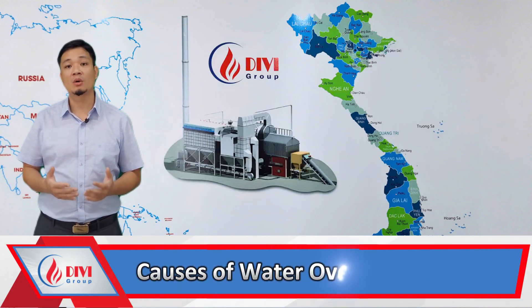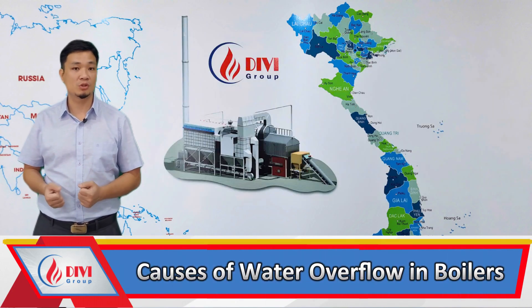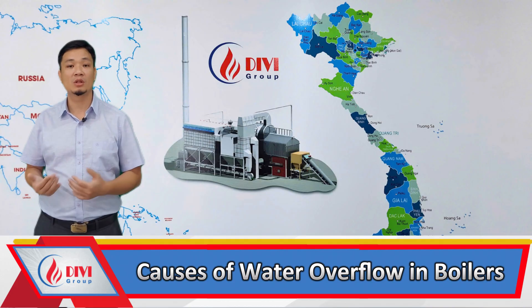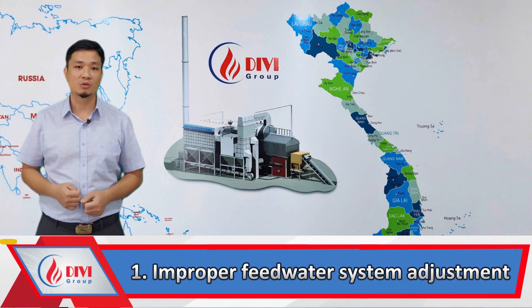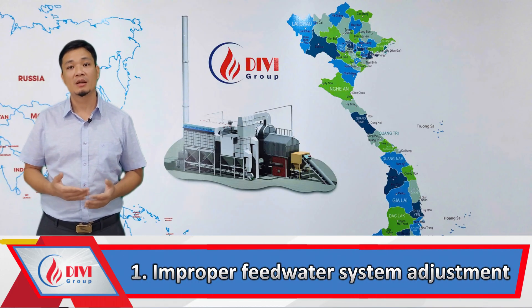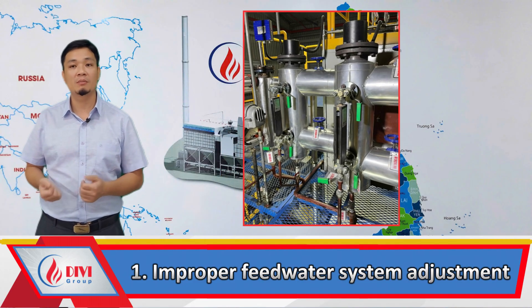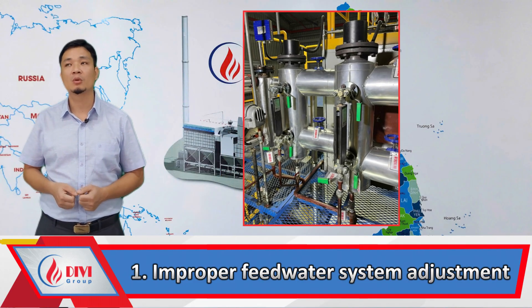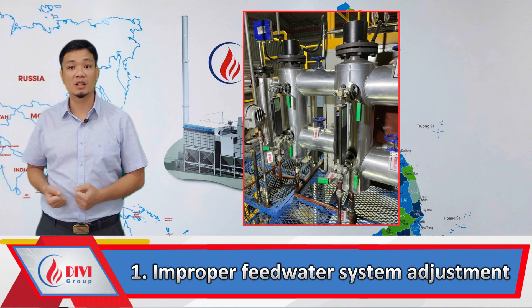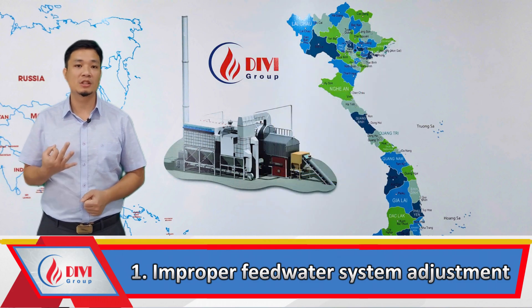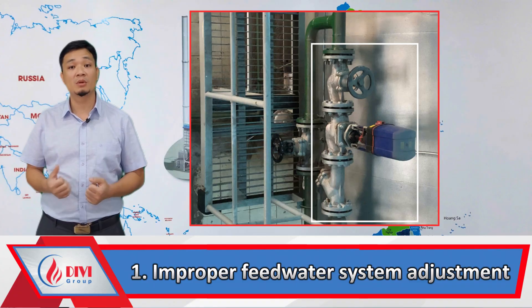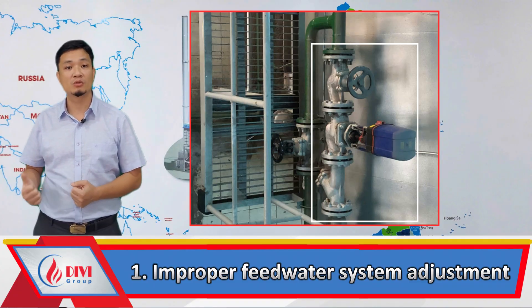Causes of water overflow in boilers. Cause one: improper feed water system adjustment. The water level sensor or level control system is not functioning correctly, causing excessive water supply beyond the safety threshold. In the case of a feed water system controlled by valves, if the valve is faulty and does not close tightly when the water reaches the correct level, an overflow can occur.